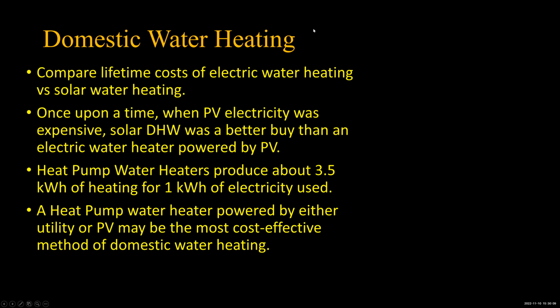Here's a Q&A: heat pump water heaters also dehumidify the air used to source the heat pump. Yes, exactly—they cool it and dehumidify it. So if you're living in Florida and your water heater's out in your garage, it gives you a little additional air conditioning out there. It's not like putting a 3-ton air conditioner in your garage, because your heat pump water heater only runs when it has to heat water. If you've got a tank full of hot water and don't need to shower, run the dishwasher, or do laundry for a while, it's going to shut off. But folks I know who have them in their garage are quite pleased that they give a bit of relief from the humidity.